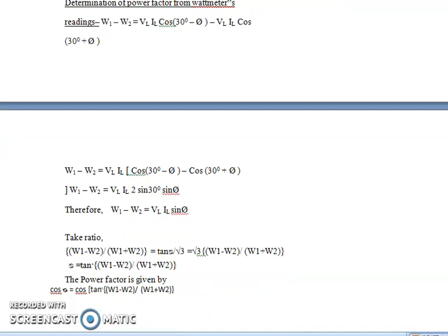You require this formula for the power factor. They may ask you the power factor, or they may ask the angle also. Remember, this is the most important formula, the power factor formula: cos phi is equal to cos of tan inverse of root 3 times (W1 minus W2) divided by (W1 plus W2). This shows that in 3-phase circuits, 2 wattmeters are sufficient to measure the power. We derived W1 minus W2, W1 plus W2, and the power factor equation from the 3-phase system.